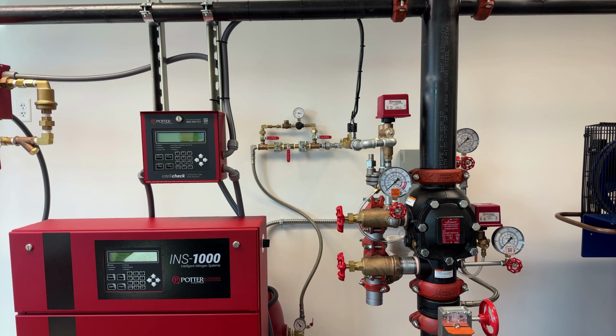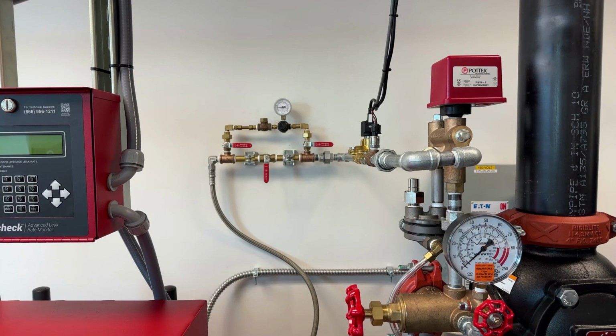The AAMD should be installed in an accessible location to permit periodic inspection and field adjustment. In accordance with NFPA standards, each sprinkler system is required to have its own dedicated air maintenance device. It can be installed in any 360-degree orientation to accommodate a number of installation applications. Once you have determined the appropriate location of the Advanced AAMD and physically installed it into the supply line, you must then determine the correct operating pressure required for the sprinkler system. This pressure setting is provided by the manufacturer of the dry pipe, pre-action, or deluge valve. This information can often be found in the valve manufacturer's datasheet.